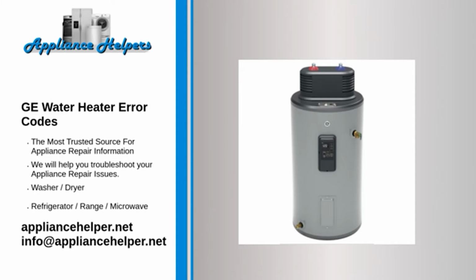resistance. Code FB. Problem: compressor discharge temperature not stable. Fix: the T4 sensor compressor outlet temperature must be greater than 120 degrees Fahrenheit after 30 minutes of runtime. Disconnect power or unplug the water heater and check T4 sensor mounting, wiring, and ohm resistance. Code FC. Problem: evaporator frosted over. Fix: the T3A sensor evaporator inlet temperature must be greater than 20 degrees Fahrenheit after 30 minutes of runtime. Disconnect power or unplug the water heater and check T3A sensor mounting, wiring, and ohm resistance.